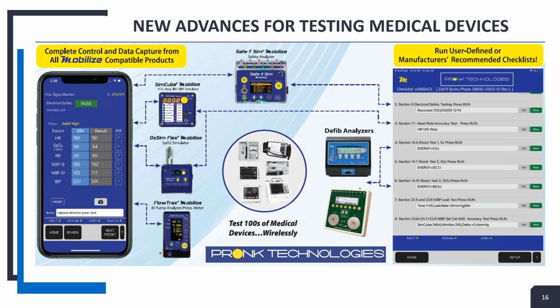So in this case, it's going to want to do an earth leakage test, and it's going to have you do an applied parts leakage test, both ground and what's referred to as ISO. The mains on applied parts, 120 volts AC on the snaps. That's what it's doing there, and it's doing it according to the manufacturer. So what's helpful is it takes the guesswork out of what am I supposed to test, what's the pass-fail limit.